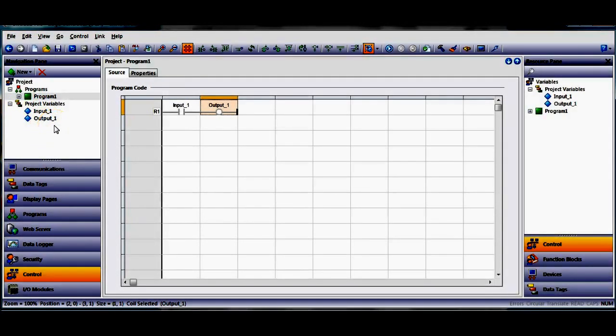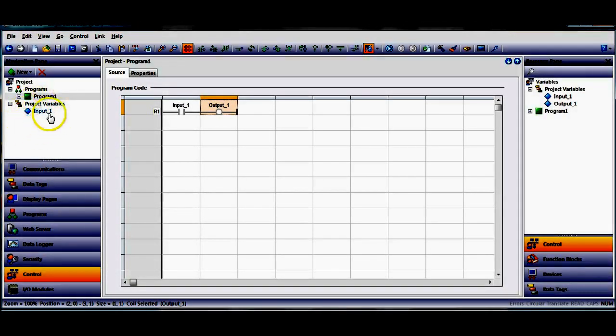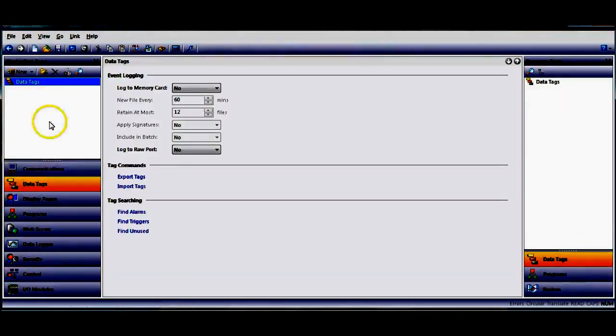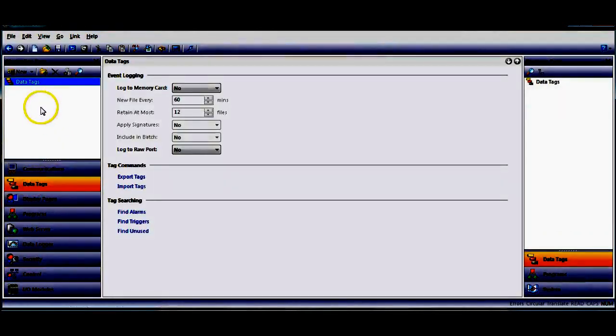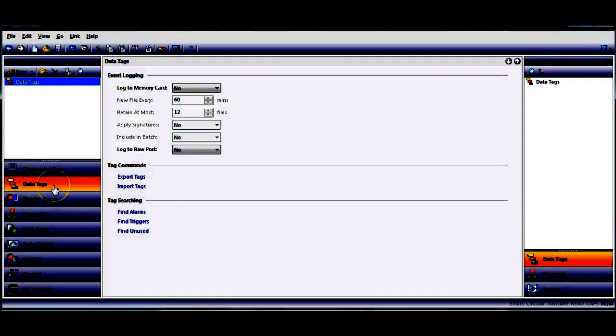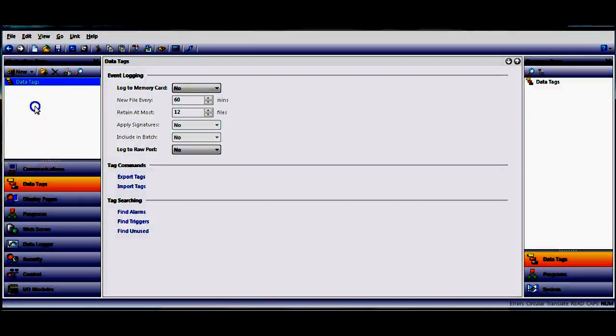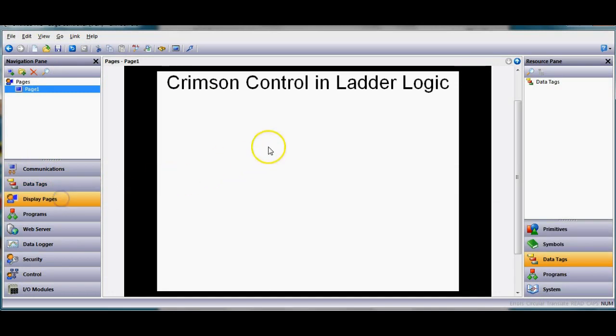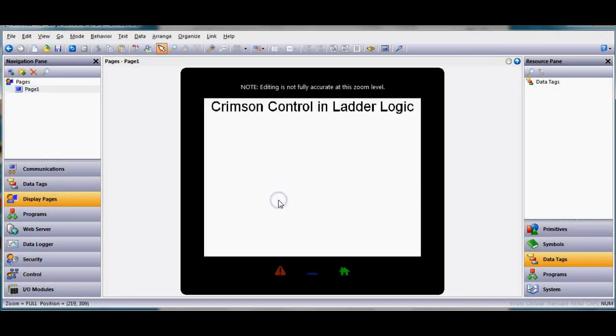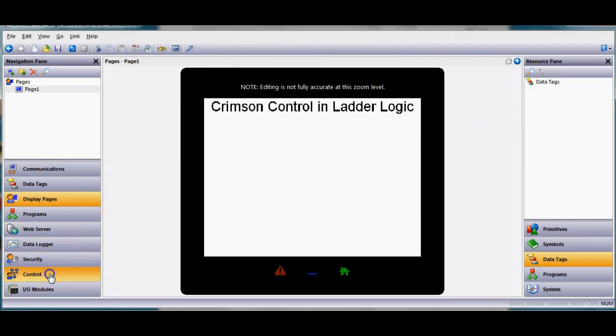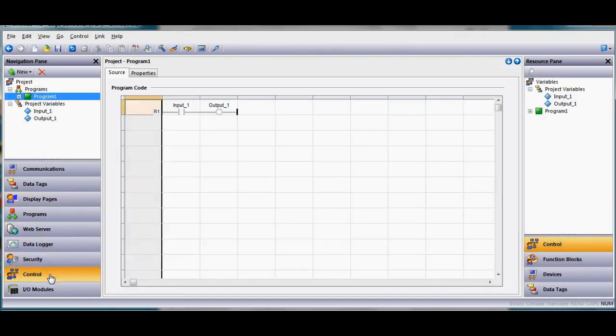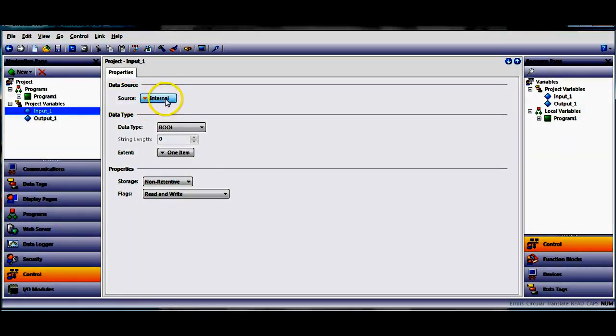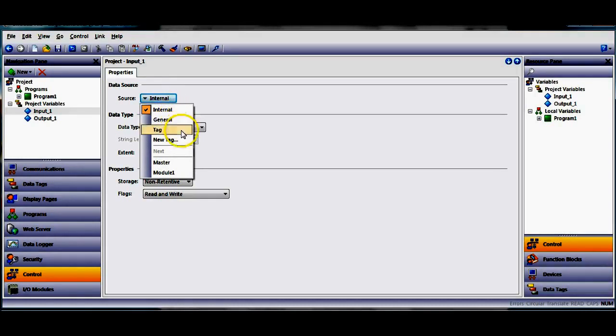You can see over here they show up now. Well these variables right here only exist within the crimson control program, they're not currently available in your HMI program. If you look over here this is where you're normally used to using tags within crimson 3.0, as you can see right now there's no tags in at all. If I wanted to put these on the display page here there's no way to do it because they don't show up over on the side. So what I'm gonna do is over here to the left hand side in the crimson control area and I'm gonna click on my input one and I want to connect this tag to a tag that would reside in my HMI environment. So right here where it says source hit the pull down and I'm gonna declare this as a new tag.